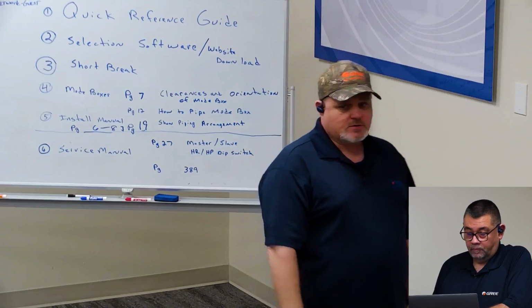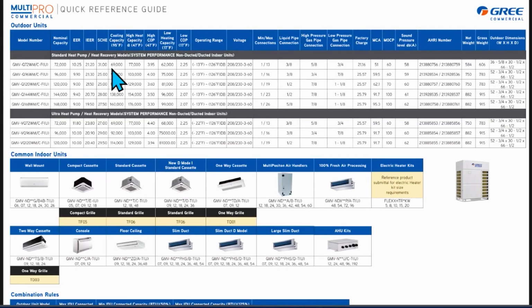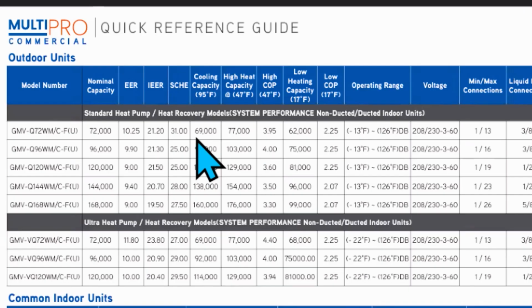So you're taking the heat out of that server room to protect the servers, and you're able to transport that heat into the office spaces where people need heat. That's why that number jumps up so much, because basically it's energy management. You're not wasting heat. There are other HVAC systems out there now that take heat from one space and dump it into the water heaters. It's all energy management, and VRF does a great job with that when you're doing heat recovery.